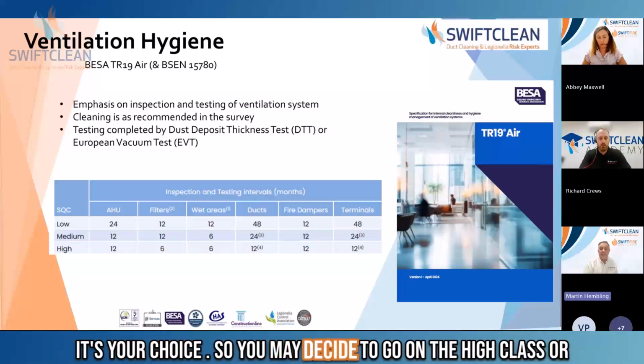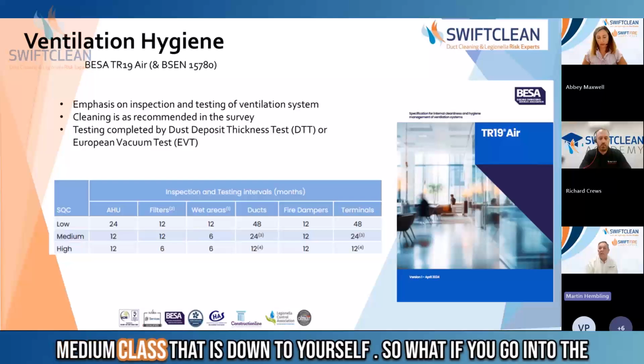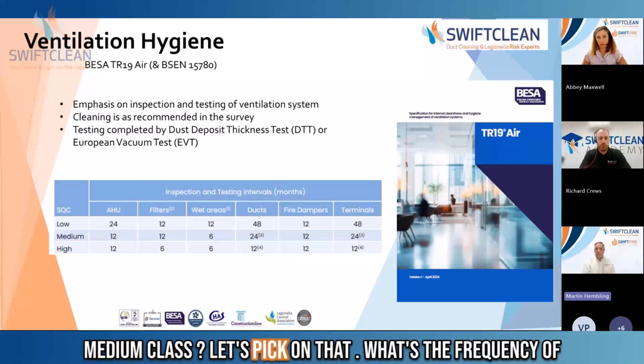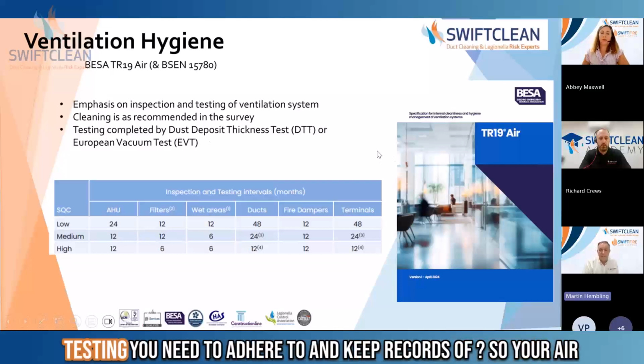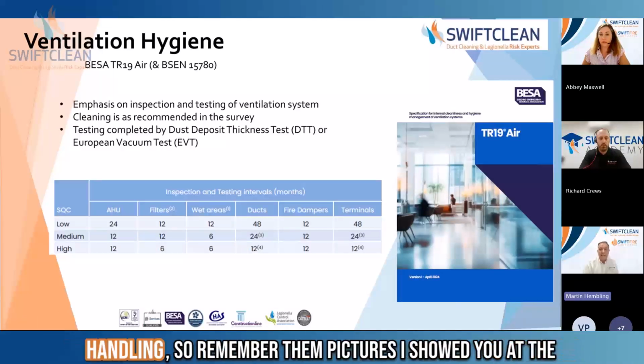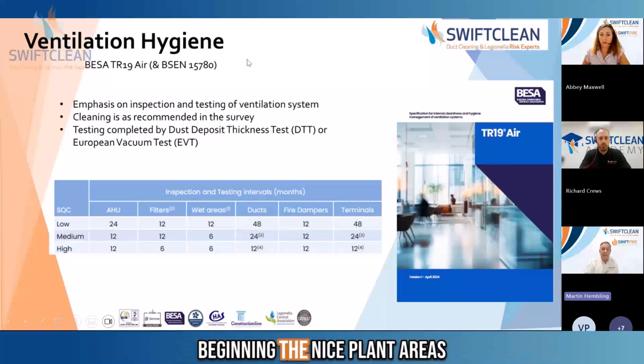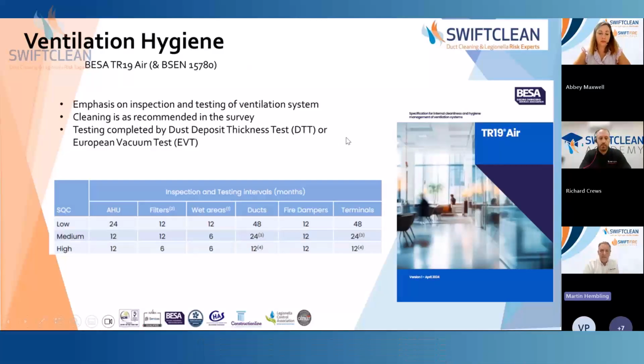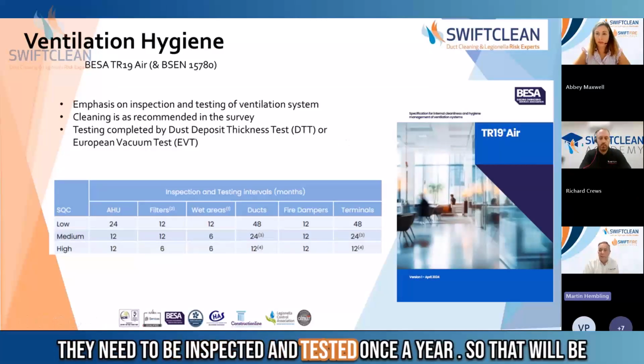So you may decide to go on the high class or medium class, that is down to yourself. So what if you go into the medium class? Let's pick on that. What's the frequency of testing you need to adhere to and keep records of? So your air handling, so remember them pictures I showed you at the beginning, the nice plant areas, they need to be inspected and tested once a year.